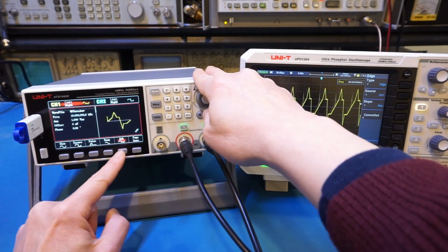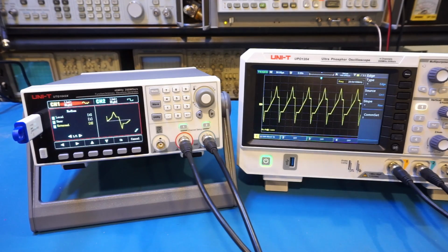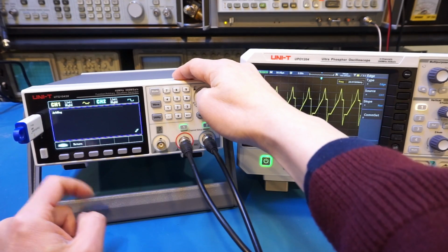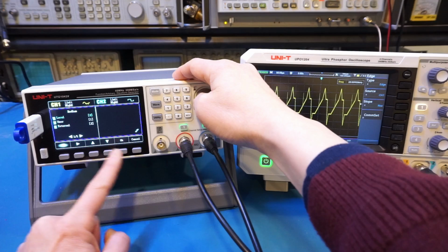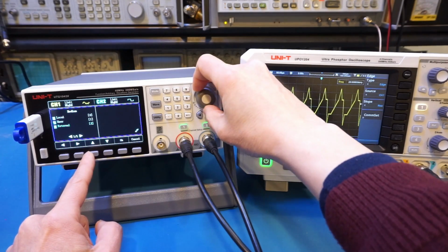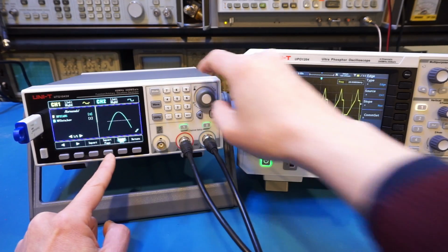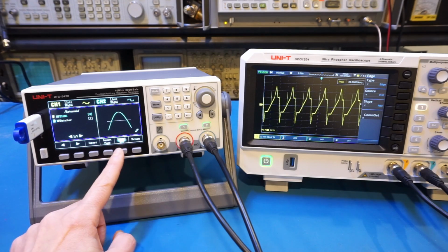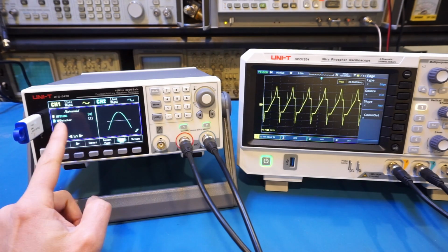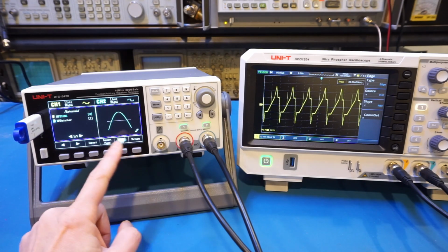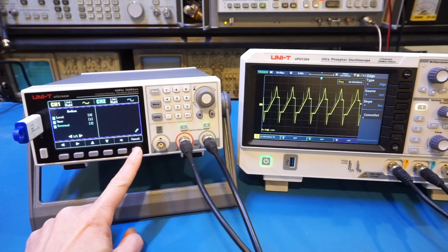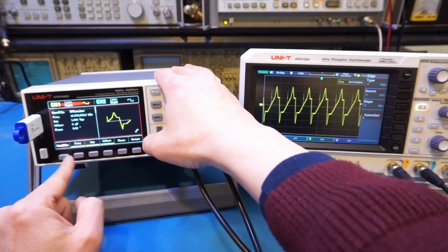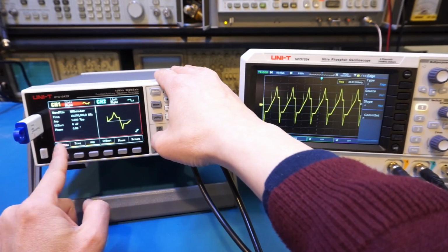And let's go back here. Let's just take another look. Alternatively, you could also come to the utility here, and you will see Arbitrary Waveform Manager. And in Arbitrary Waveform Manager, you can see here, we can also use that to get to the actual waveform here. Now, here we have an option to import the waveform into the onboard memory here. So, for example, if I do import all, of course, we only have this one arbitrary waveform currently, but I have imported it, and let's return here. So let's take a look. And you can see we have the arbitrary waveform data.